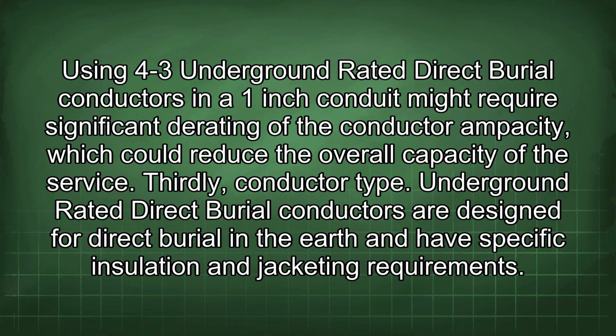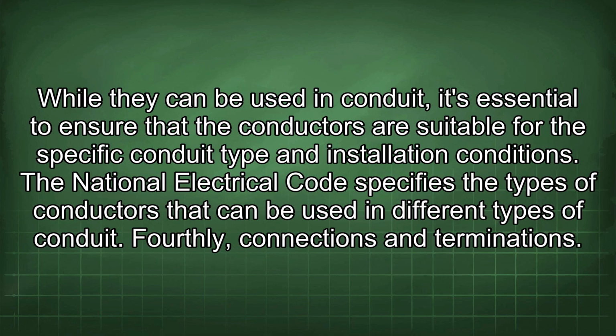Thirdly, conductor type. Underground rated direct burial conductors are designed for direct burial in the earth and have specific insulation and jacketing requirements. While they can be used in conduit, it's essential to ensure that the conductors are suitable for the specific conduit type and installation conditions. The National Electrical Code specifies the types of conductors that can be used in different types of conduit.